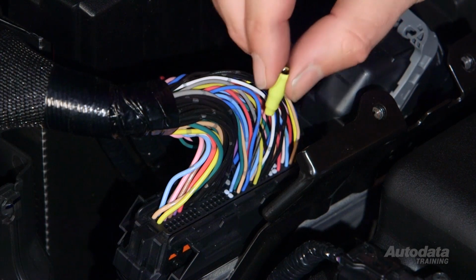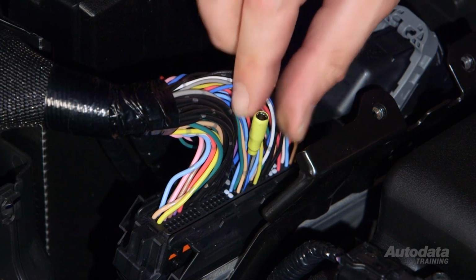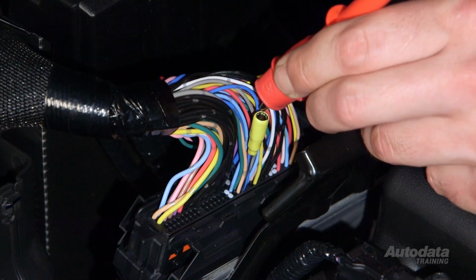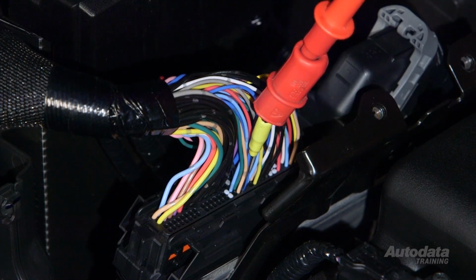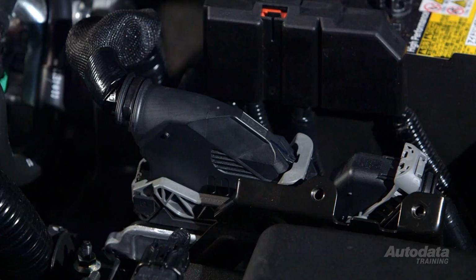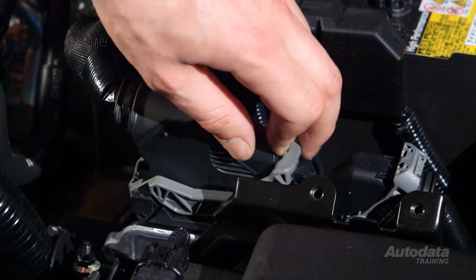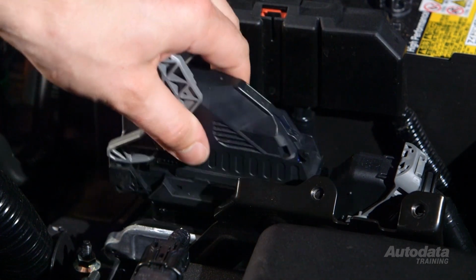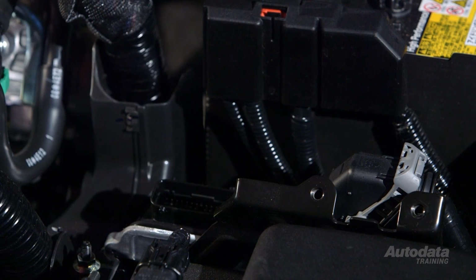The last check will be back probing the ECM connector. If no voltage is found here, it'll be the connector or the ECM. Unplug the ECM connector and check for corrosion and the correct terminal tension. If this checks out, the fault will be in the ECM.